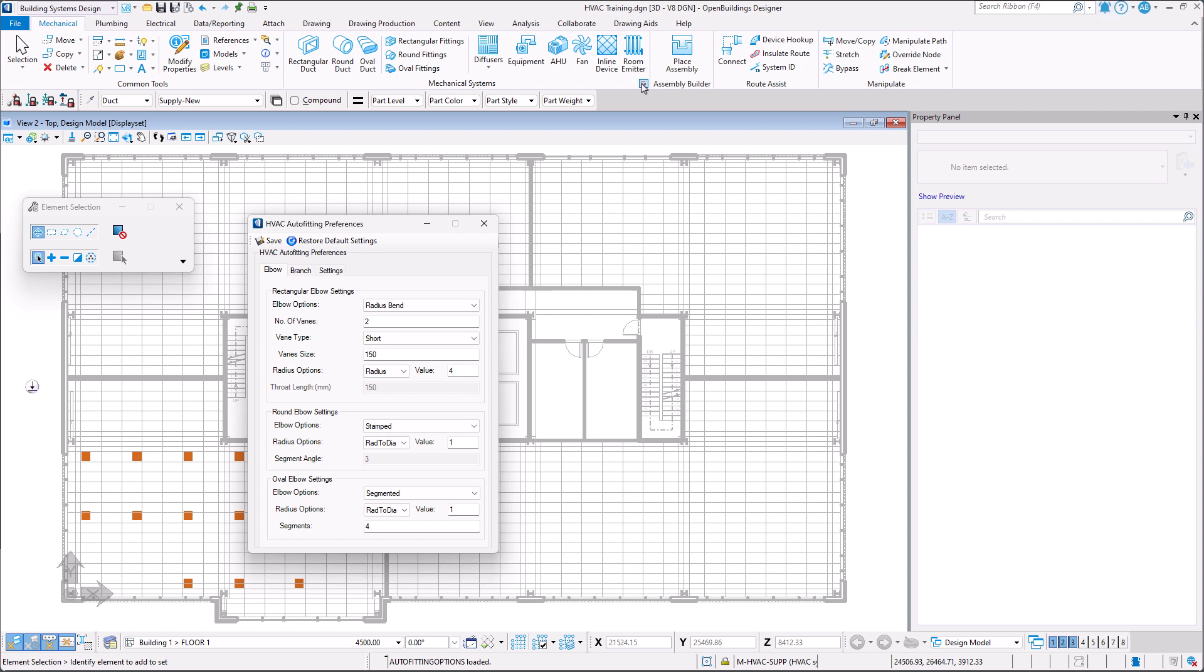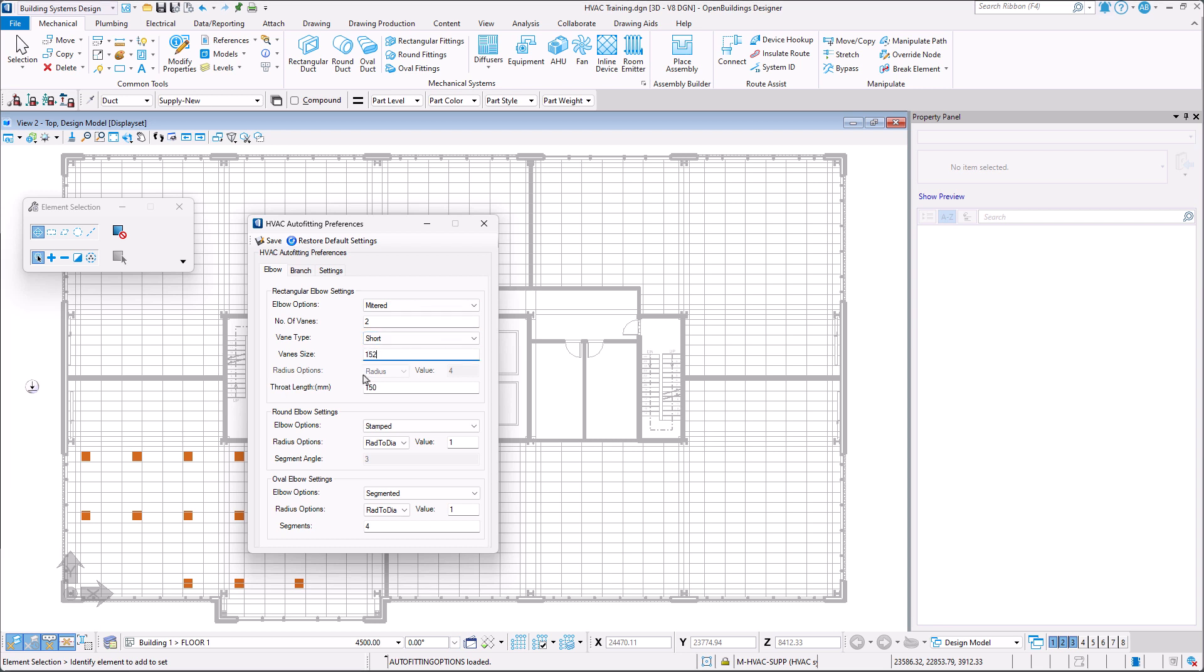In the HVAC auto fitting preferences dialog box in the elbow tab we must set the elbow options to mitered and the size of the vanes as well as the throat length to 152 millimeters.